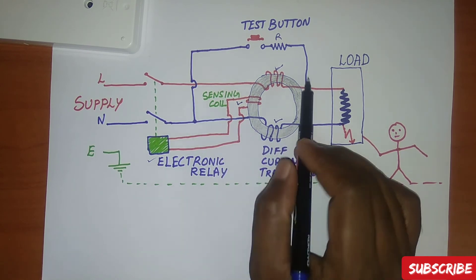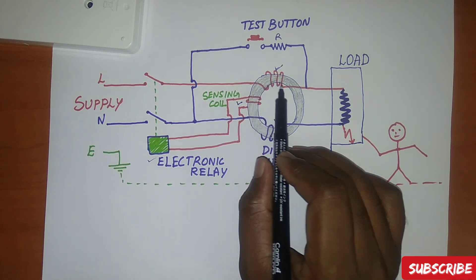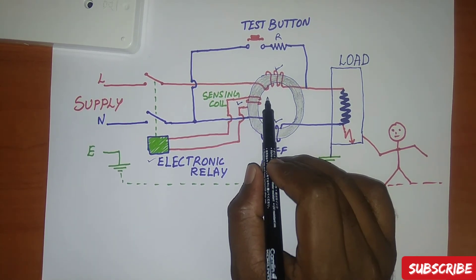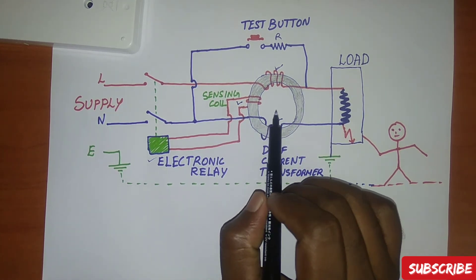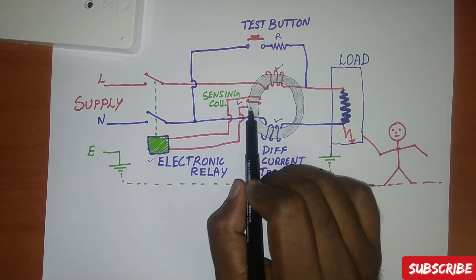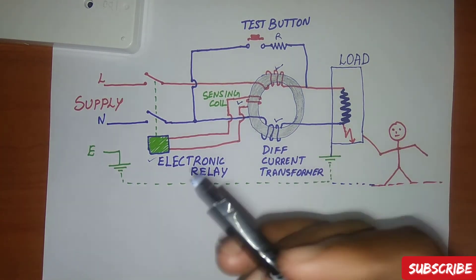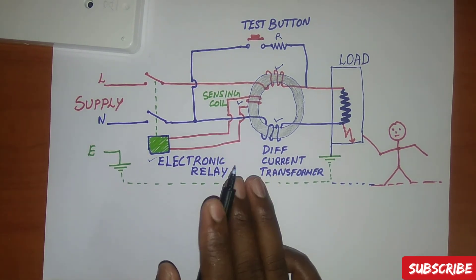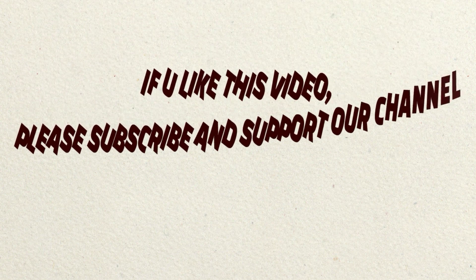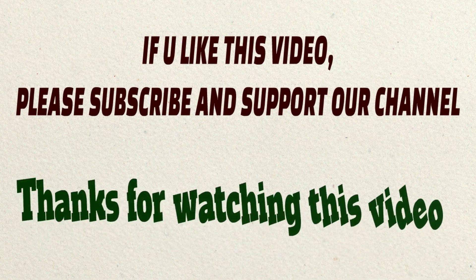The test button is connected between neutral and line through a resistor. When you press the test button, it allows the correct operation of the device to be verified by passing a small current, simulating a fault by creating an imbalance in the sense coil. If the RCD does not trip when the button is pressed, the device must be replaced. RCD testing should be done on a regular basis. My next video is on the difference between ELCB and RCD — please subscribe and support the channel. Thanks for watching.